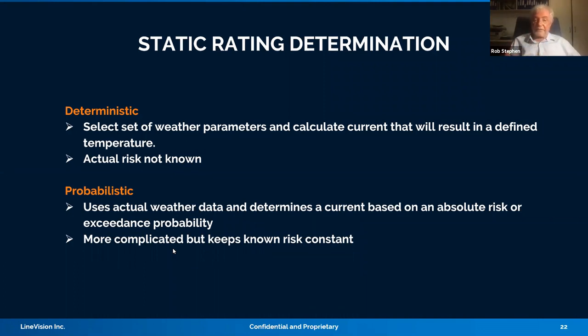The next one that you might have heard of is a probabilistic rating, which uses actual weather data, either on an hourly basis or, depending on what you can actually get, at a lot more accurate intervals than that. And it determines the current based on an absolute risk or exceedance probability. This is used in South Africa, where we did a lot of development with CIGRE, and also in the UK, where they use an exceedance probability on their lines, and it resulted in uprating of the lines.